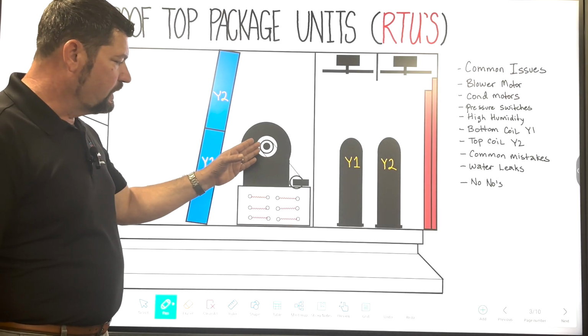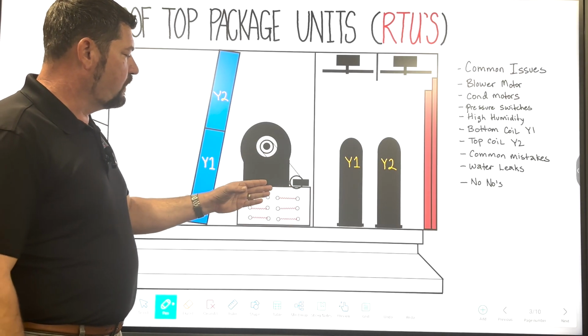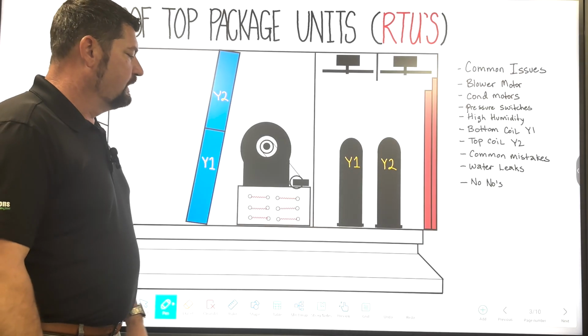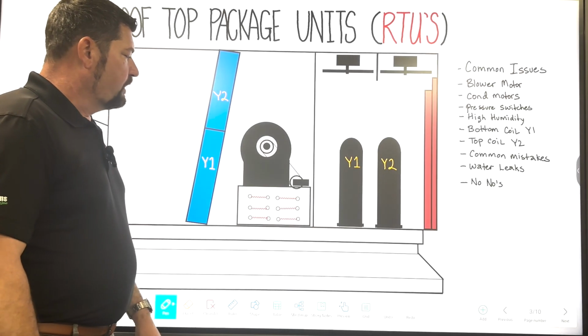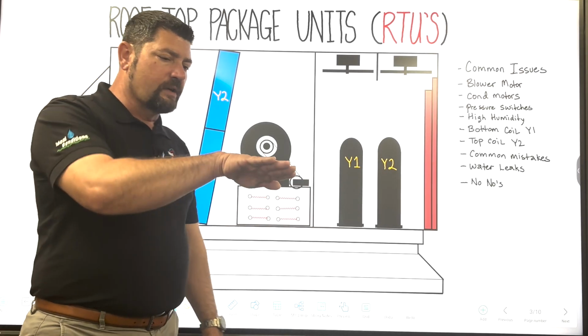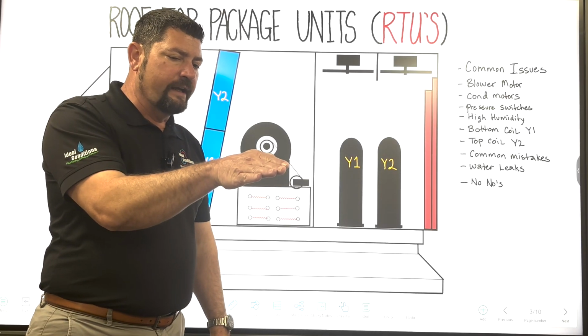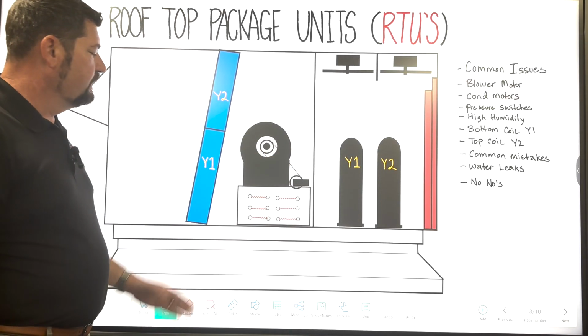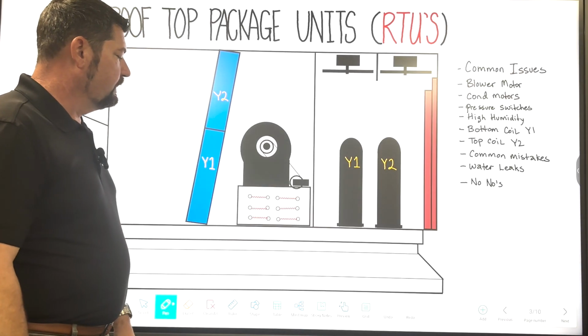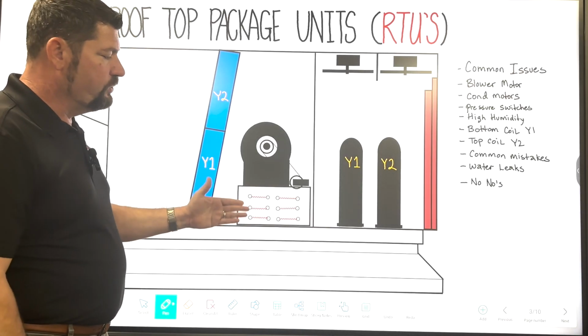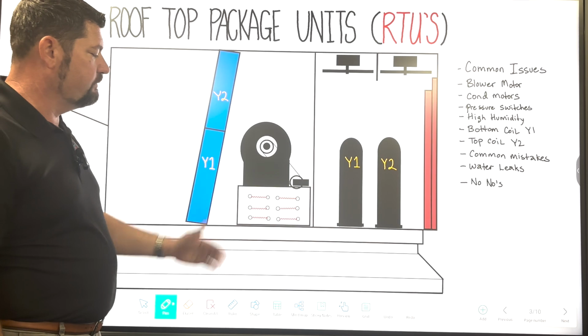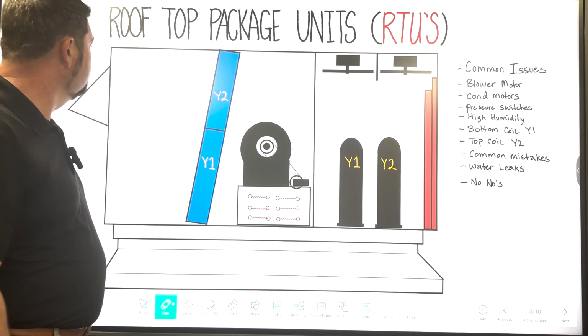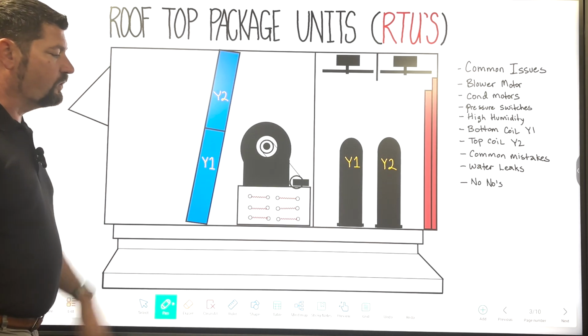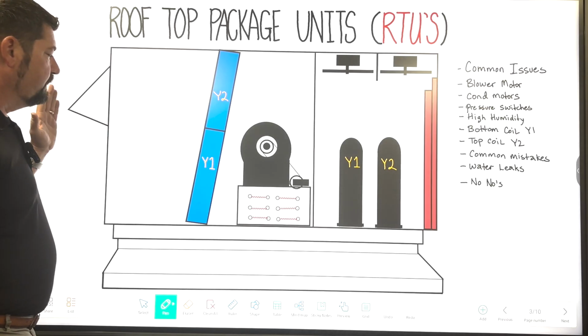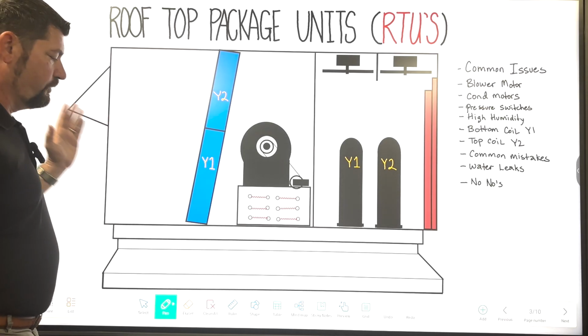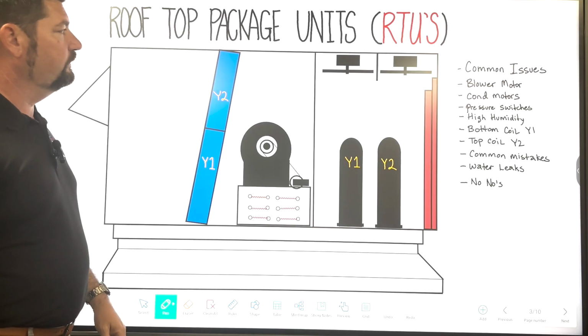Motors not turning at the proper RPMs and belts flopping off. Belts not being aligned properly, so they're not riding just right, so they start to ride on their edge and they flop off. Obviously, heat strips, they're not fused properly, so a lot of times we see these things not even connected. We have fresh airs that aren't installed, and when they are installed, they're either all the way closed or all the way open. They're not in the proper positions.